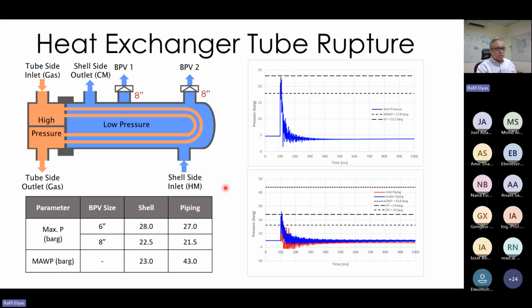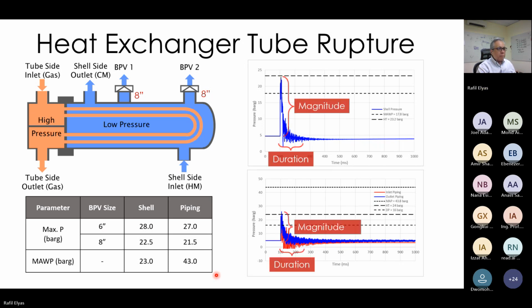In order to reduce that, we have to go with an 8-inch valve instead. If we take a look at the max pressure over here, for 6-inch we saw the max was about 28, 27. With 8-inch, it was like 22 and 21. MAWP in this case was about 23. So what you get from a dynamic simulation is magnitude and duration. How much and how long is it going to occur?